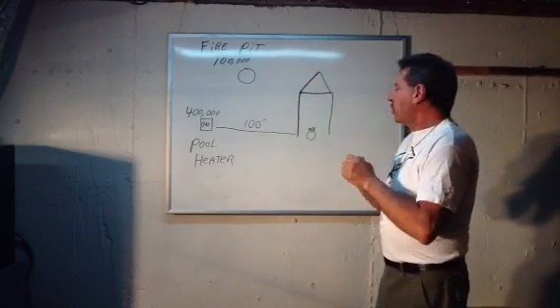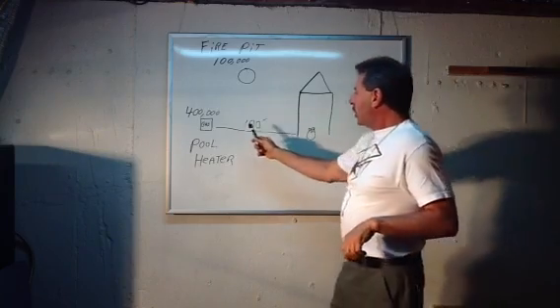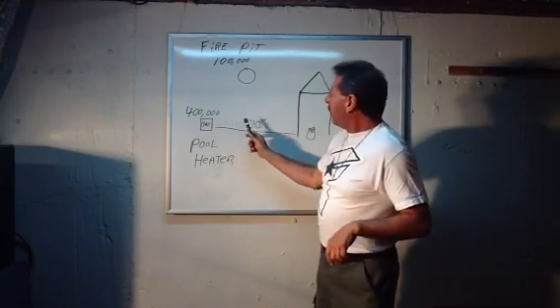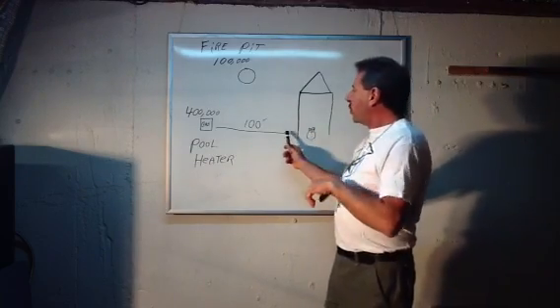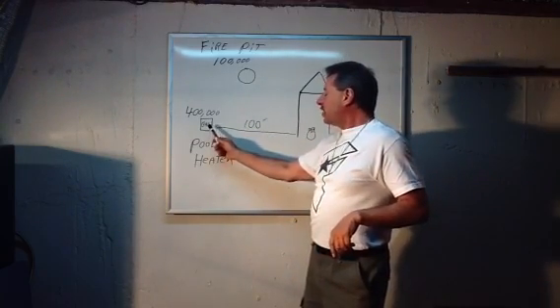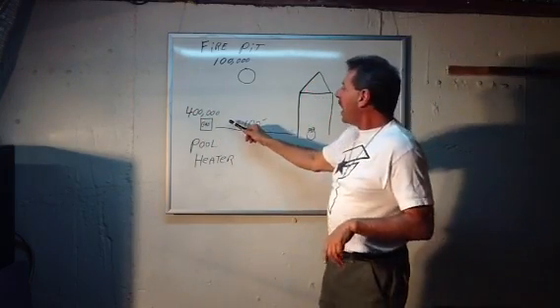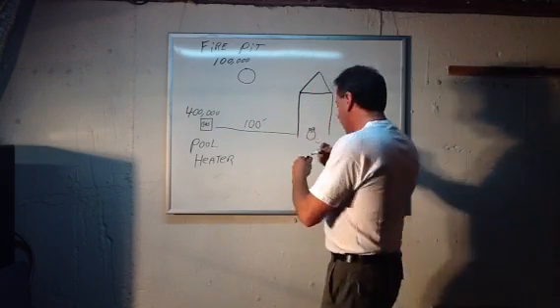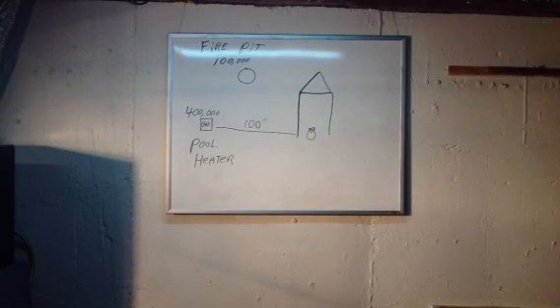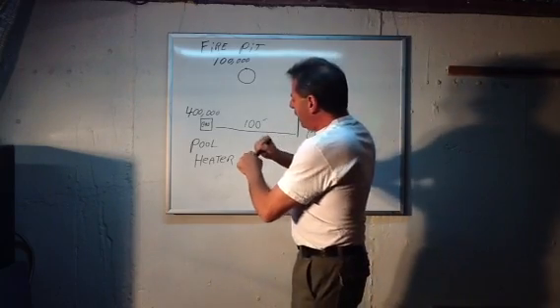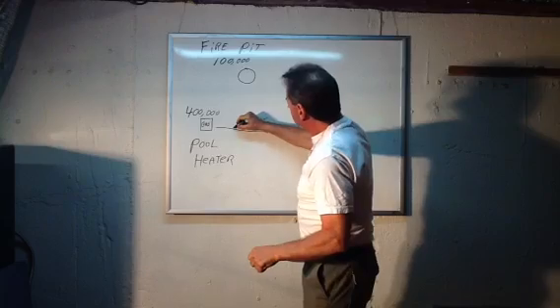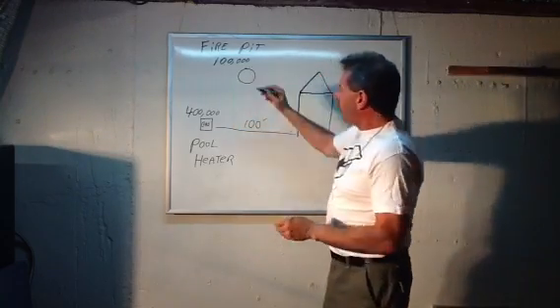So what I had to do was look at the gas meter, look at the pool heater, get the distance of 100 feet, and find out what size pipe would get me at least 400,000 BTUs. That was the first thing, plus have enough to jump over later to add a second gas line over to the fire pit, which is 100,000 BTUs.